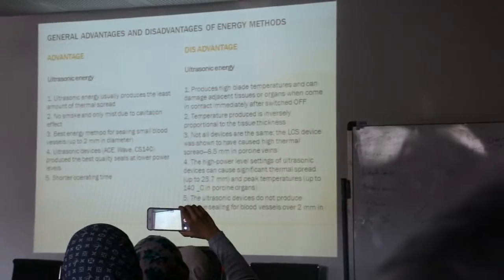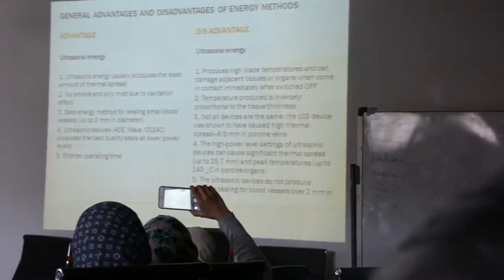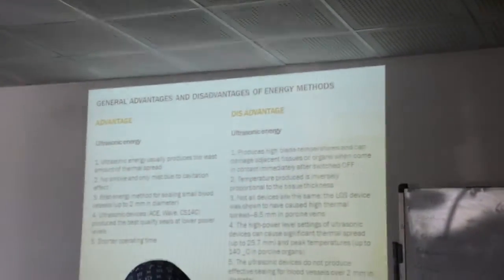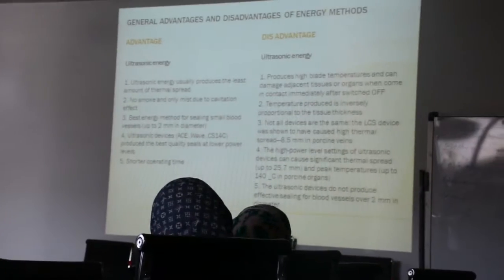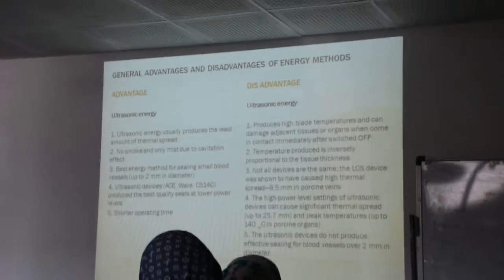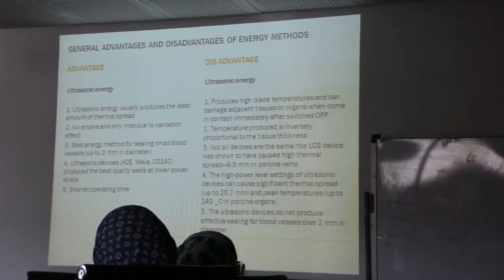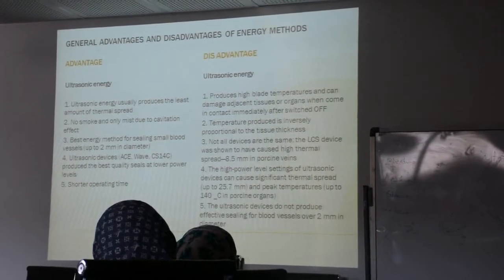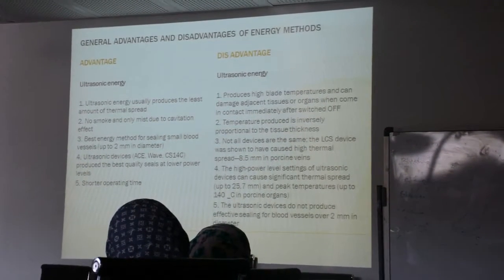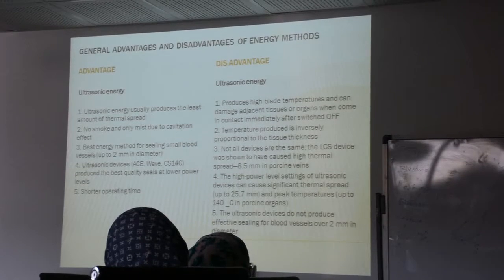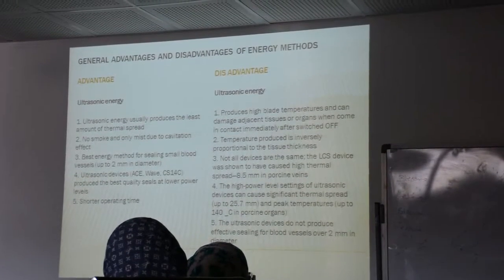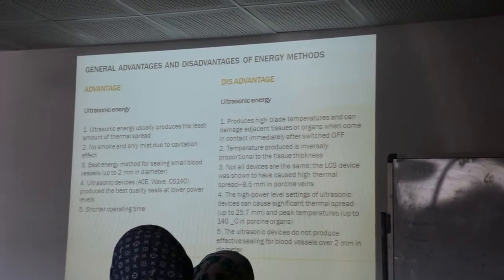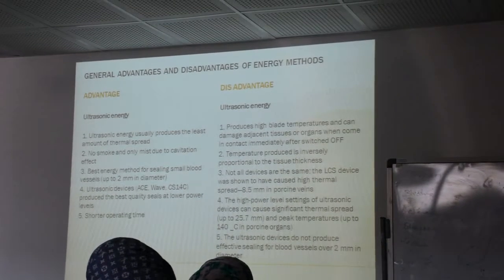Disadvantage of ultrasonic energy: it produces high blade temperature and can damage adjacent tissue or organs when they come in contact immediately after switch off. The temperature produced is inversely proportional to the tissue thickness. Not all devices are the same.